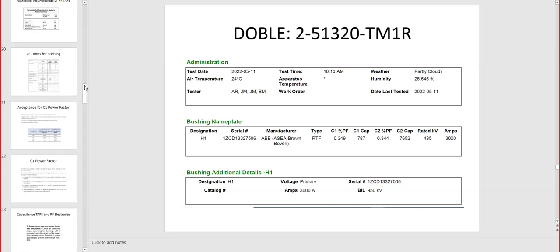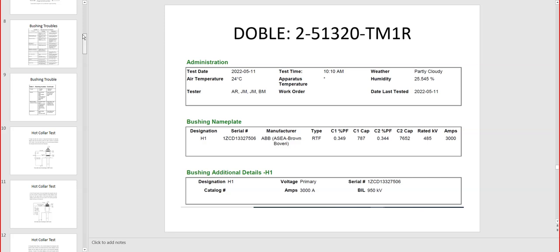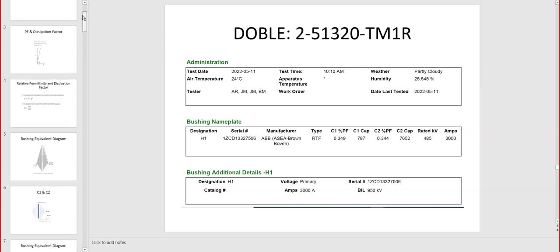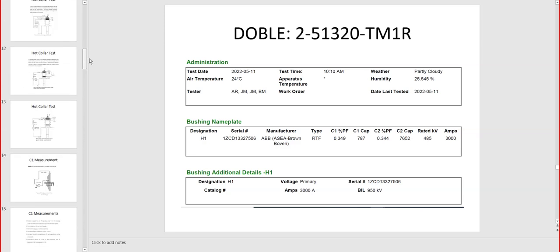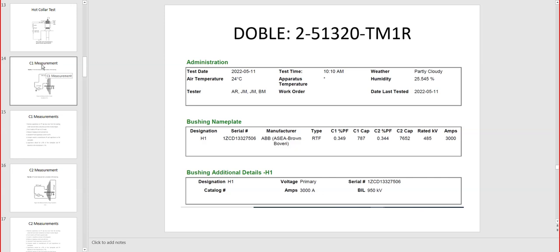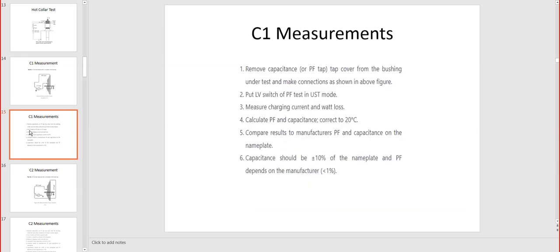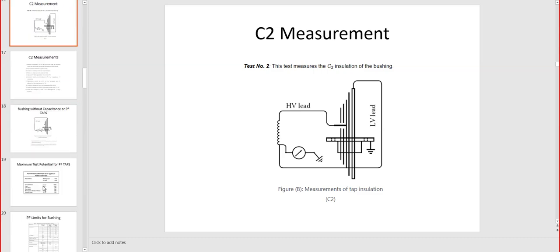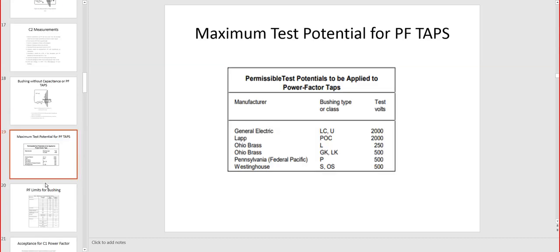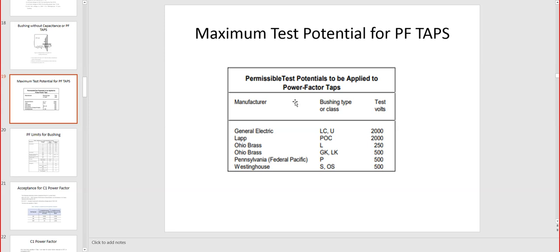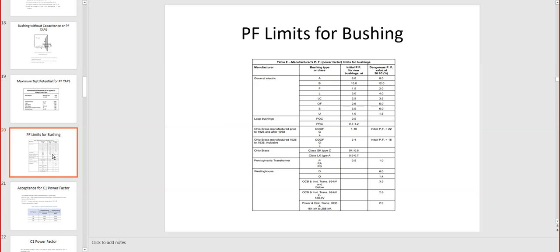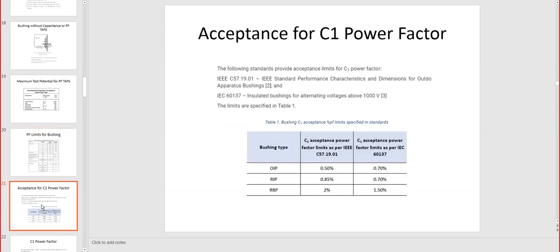You must have mentioned an IEEE standard. Sorry, I might have missed that. Yeah, we have mentioned here, it is actually two standards, the IEEE and the international standards. We will focus on the IEEE, but also you need to have the manufacturer data for your bushing, nameplate data.